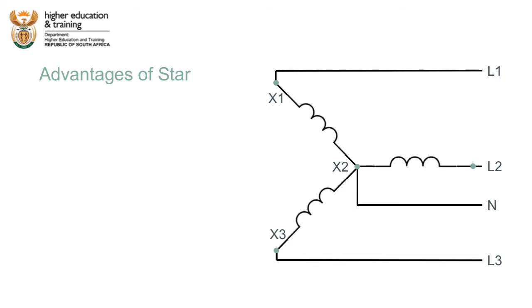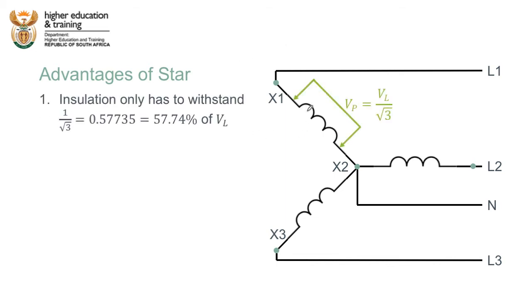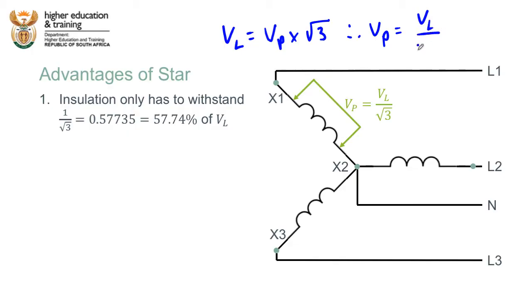Connecting a transformer in a star configuration has some advantages. The first is that the insulation around the coils only needs to withstand a portion of the full line voltage. In a star configuration, the phase voltage equals the line voltage divided by the square root of three, which is just 57.74% — a little under 58%. So in a star-configured system, the phase voltage only needs to cope with about 60% of the full line voltage, meaning the insulation doesn't need to be as robust as in a delta connection.